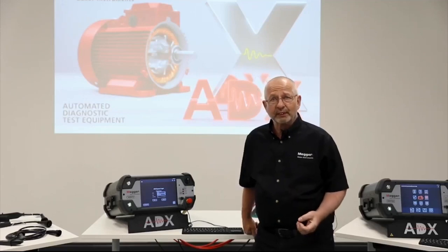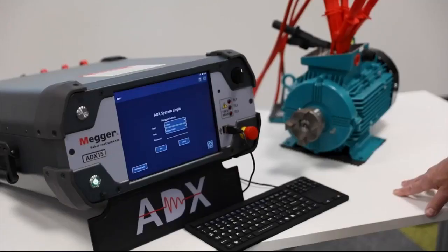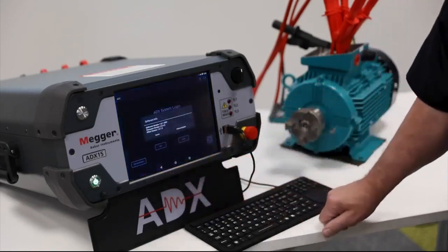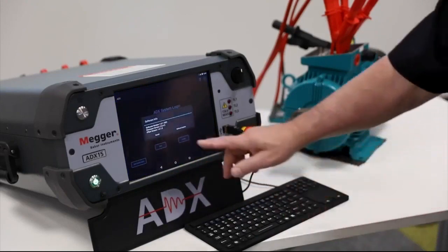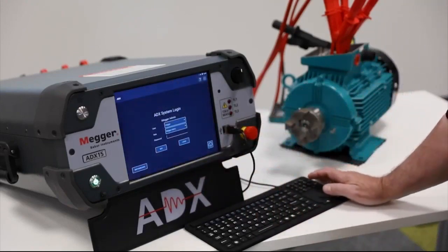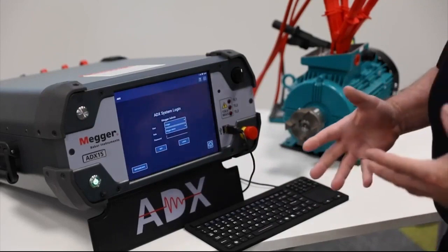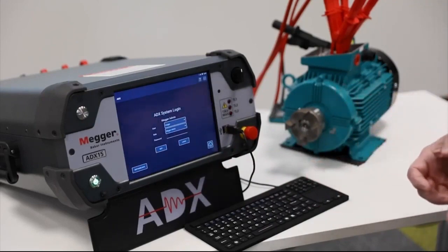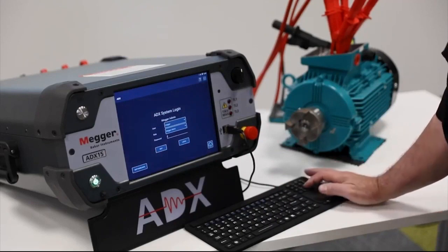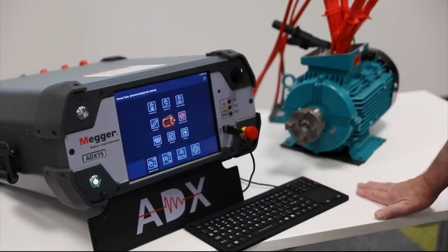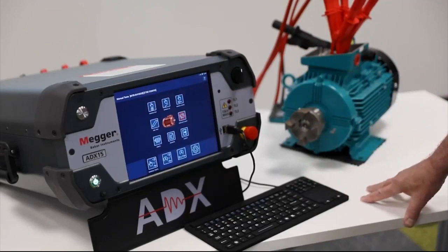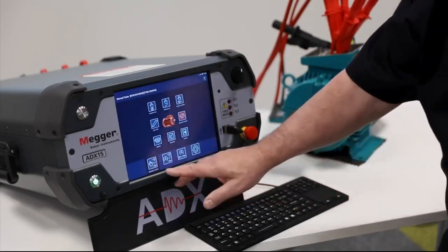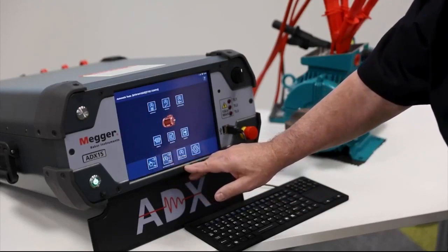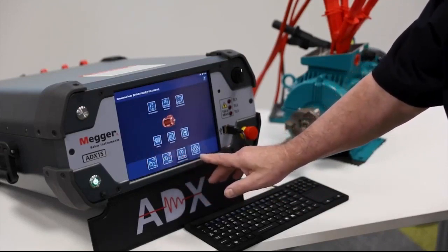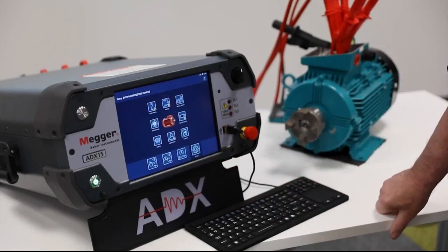Time's catching up on us, so let's have a quick look at the ADX. On startup, you're able to check the software and firmware is up to date and download updates and install them as necessary. As we log in, you can see that as an admin account holder, you can create user IDs and roles for your team. Logging into the ADX with the code will then come to the splash screen, which is the return screen that you'll always come to in ADX. In here we've got manual testing, automatic testing, sequence testing, and most importantly, setup screen.